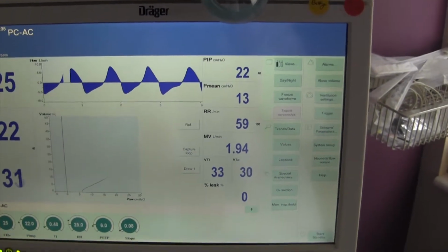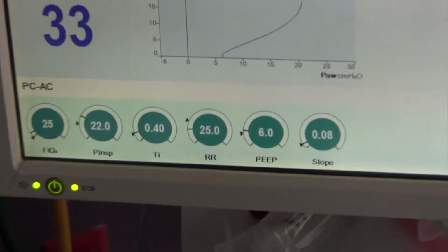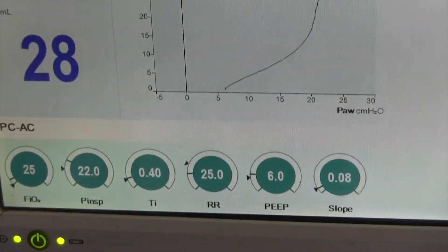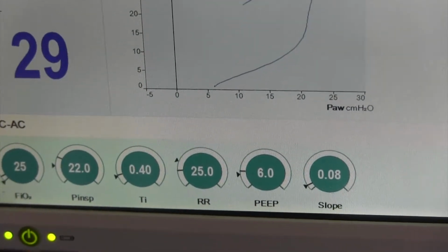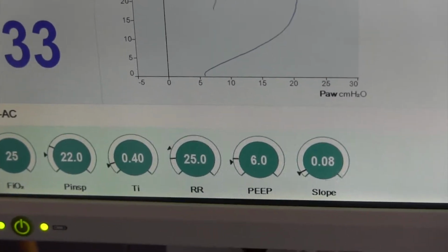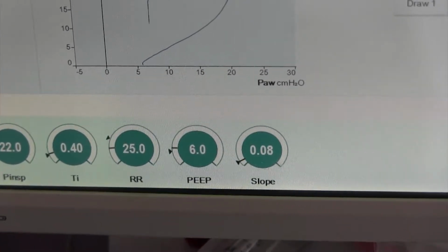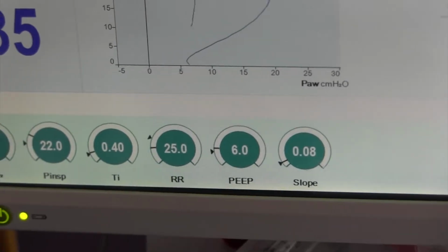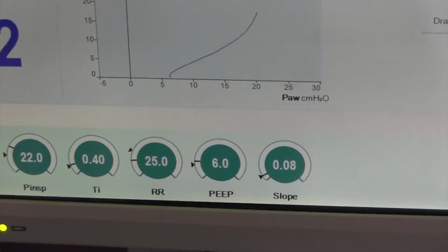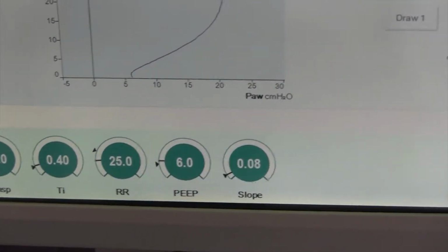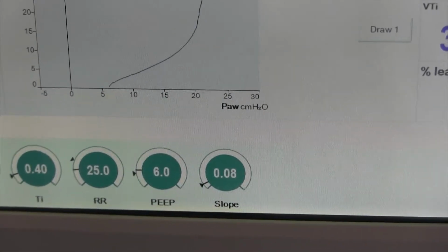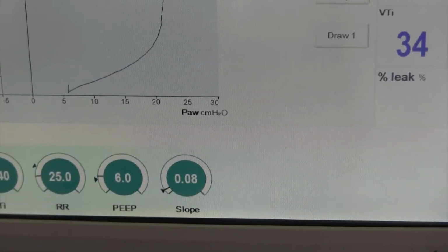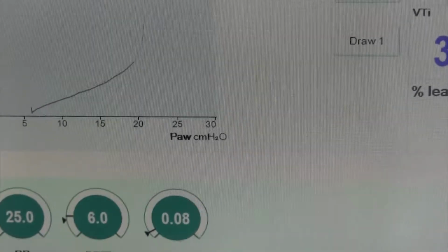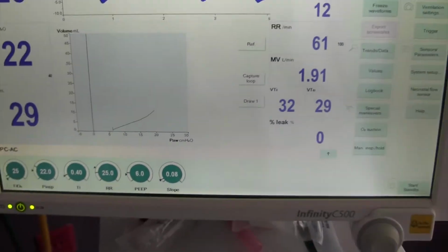You'll notice that there are a number of key pieces of info that are displayed right away on this first screen. The things that I would point out particularly are, if you look at the bottom of the screen here, you'll see numbers that tell you what your fraction of inspired oxygen are. This patient happens to be in a pressure mode, and so it has a peak inspiratory pressure, an I time, which is measured TI, respiratory rate, PEEP, and then a slope, which is a more advanced piece of setting that we don't need to talk about today.